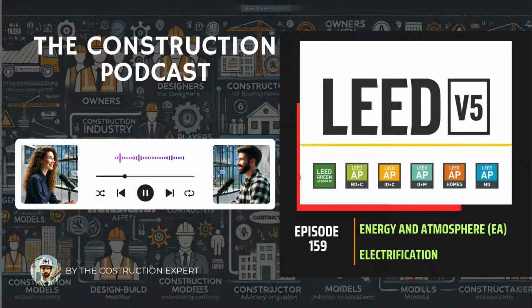Second, use high-efficiency electric heat pump technologies. These really are the workhorses of modern electrification for heating, cooling, and hot water. Not just basic electric resistance. Definitely not. Heat pumps, as we said, move heat. They don't just make it from electricity. Their efficiency, their COP, is just fundamentally higher, and the technology has improved massively, especially cold climate heat pumps that work effectively down to very low temperatures.